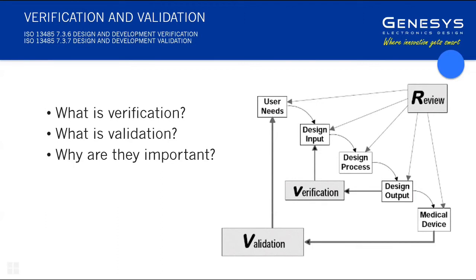Yeah, I can think of an example here because I did hear about this one. In a surgical theatre, you might have a device that has a display on it, and you say, okay, we need some numbers displayed. But in a really bright surgical theatre with lots and lots of light shining on it, the glare on the screen can be such that you can't read the numbers. Yes. So yes, the engineers said the numbers were displayed, but when you got in the operating theatres, actually you couldn't read the numbers.